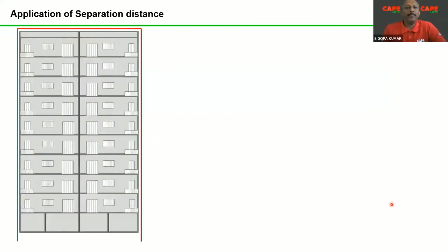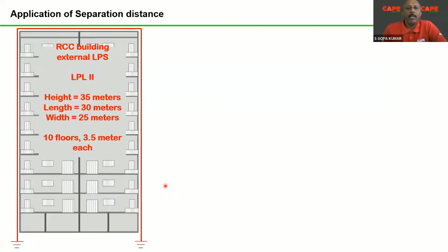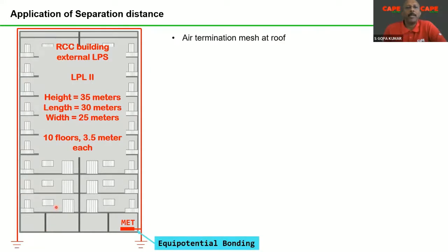With those standards, I'm trying to find out the separation distance in an RCC building where I'm going to make an external lightning protection system, a level 2 lightning protection. The height of my building is 35 meters, length 30 meters, width 25 meters. Just as an example, think of it as a 10 floor building, 3.5 meters each. I want to make an external lightning protection system with equipotential bonding at the bottom. I'm trying to find out the separation distance.